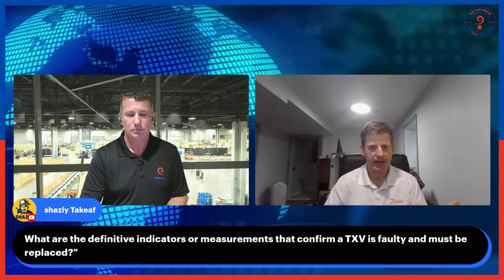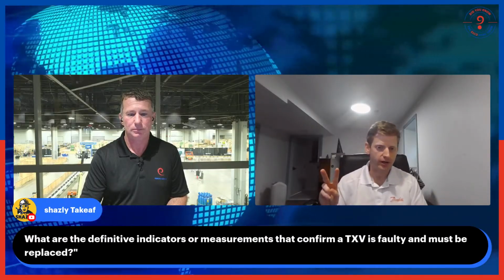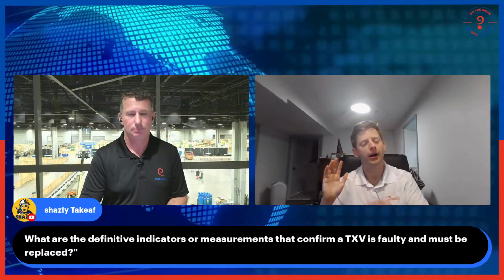When we get TXVs back, there's two major things we run into: no fault found, and then filled with contaminants. Just about every one we ever get back is that way. Sometimes we can see that it's burnt up when it's being removed. Sometimes we can't evaluate it to figure out if there was something wrong with it. But we get a lot of EXVs sent back to us, and it's almost always filled with contaminants or no fault found. And when it's no fault found, we assume that means it was diagnosed improperly, or there was another problem inside the system that prevented it from working right.